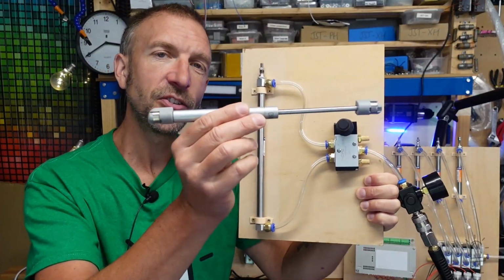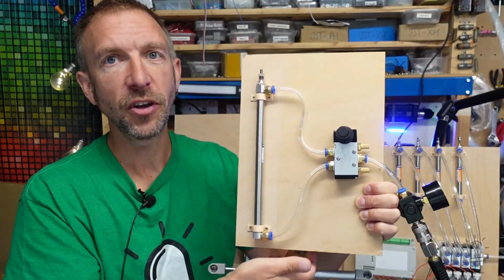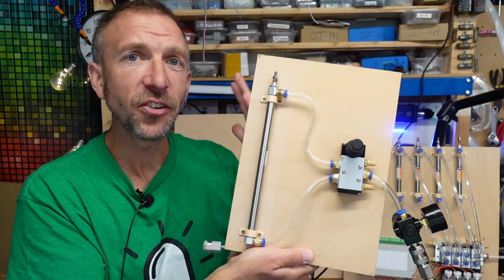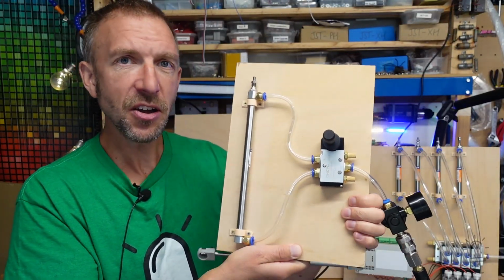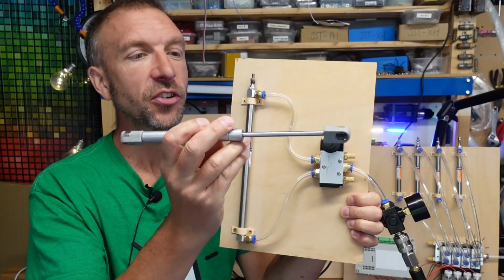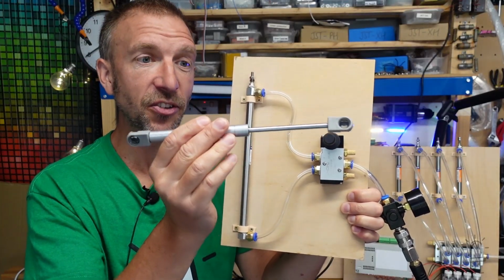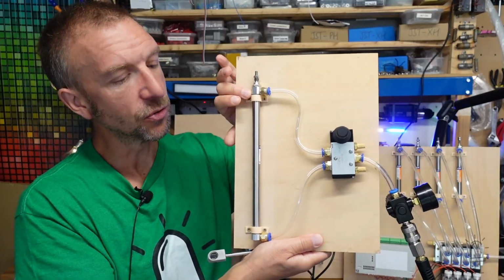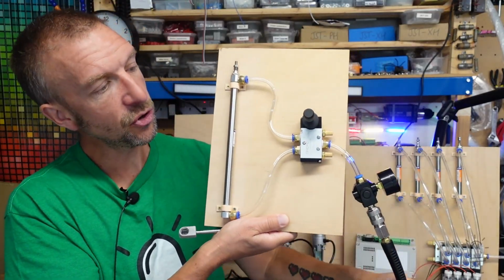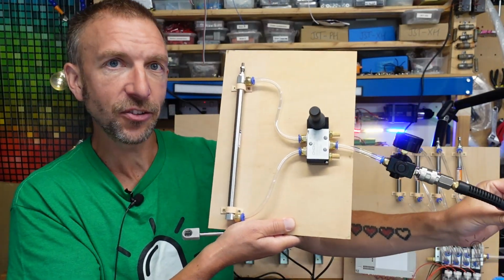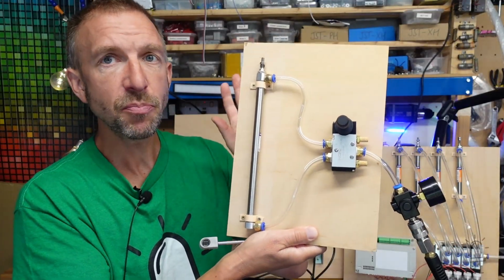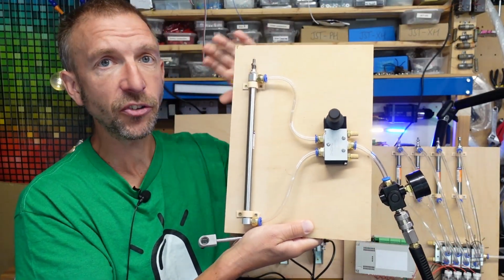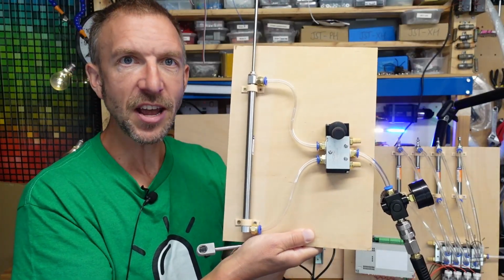So, like gas struts, these use the force of compressed gas to move the piston, and that gas is usually just air. However, unlike sealed gas struts, which contain a fixed amount of pressurised gas in a closed system, a pneumatic cylinder has ports at either end that you can hook up to an external air source. Now, if the pressure of air supplied at the base is higher than the pressure of air at the top port, the rod extends.